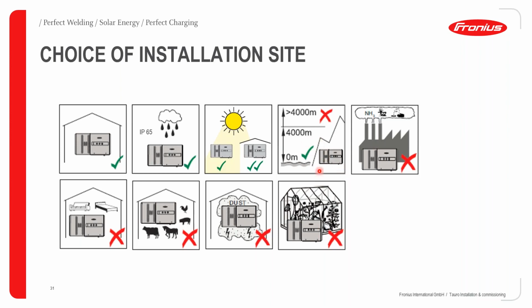The reason why altitude has an effect on PV inverters is, first, the higher you go, insulation gets further reduced. Also, the higher you are, you have a reduced cooling effect on the panels. And as you all know, if the temperature of your panels rises, the DC output automatically decreases as well. All of this will then lead to reduced AC power.